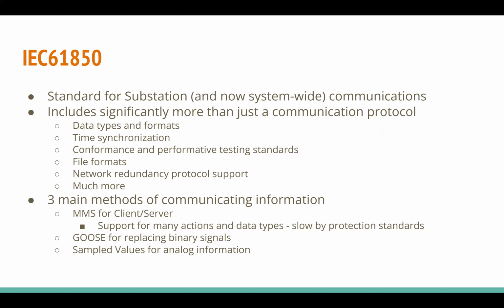It has standards for how to synchronize different relays together in terms of time, and guidelines for how you're supposed to test if your relays are even working properly, different file formats, how to set up your network so you don't have a single point of failure. There's a whole ton of stuff — I'm not even describing all of it. There's a lot in the standard.